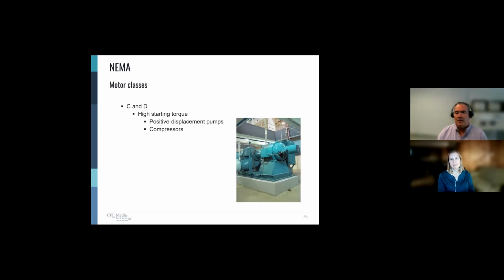C and D have much higher starting torque. Positive displacement pumps or compressors. An air compressor, in most cases, starts against a higher back pressure. Large pumps where you have a big head differential take a little more torque to get started, so you may use a motor class C or D. This is a larger motor driving a water pump in a water plant.